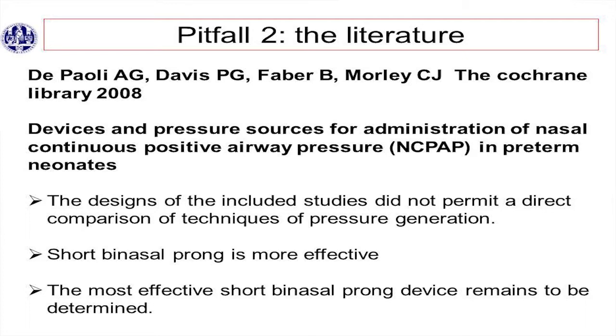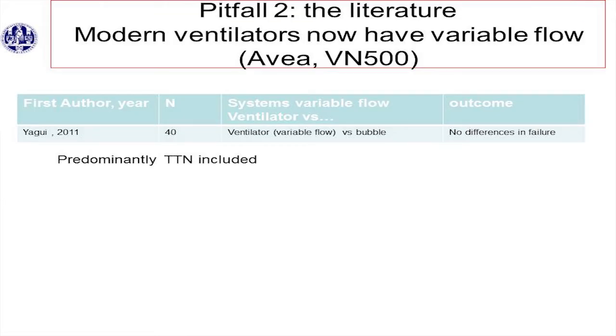The other thing I realized when reading the literature is that the studies about ventilators concern ventilators with constant flow, and now all these modern ventilators have variable flow to give CPAP. I'll give some examples, an Avea and VN500. Yagui did a study comparing a variable flow ventilator with bubble CPAP, and he saw no difference in failure of CPAP. So apparently it makes a difference whether you use a constant flow or a variable flow ventilator, but he mostly included more mature preterm infants with more wet lung than RDS.